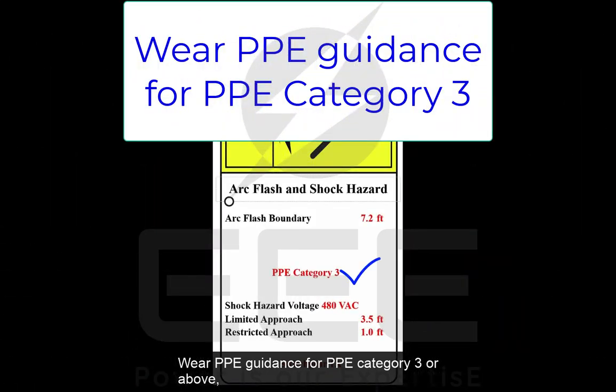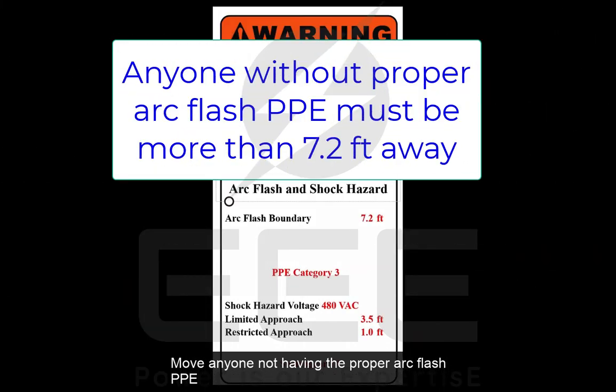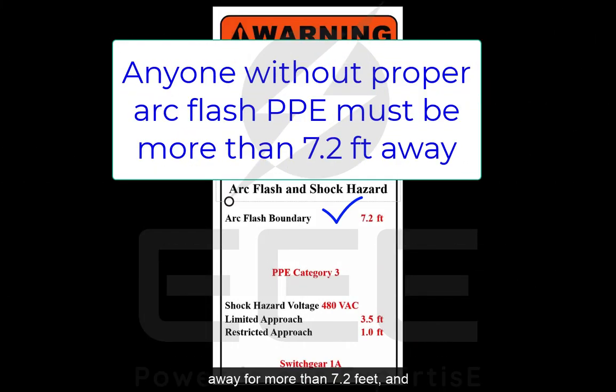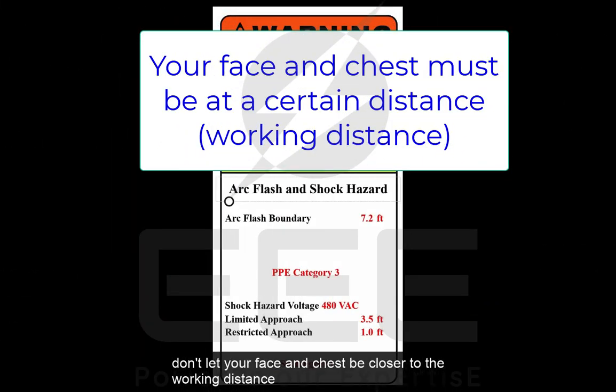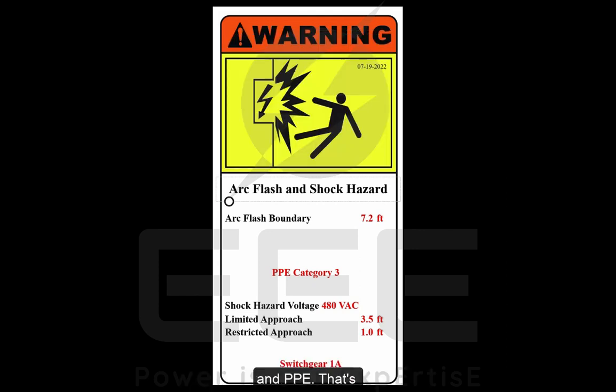Summary. Wear PPE guidance for PPE Category 3 or above. Move anyone not having the proper arc flash PPE away, more than 7.2 feet. And don't let your face and chest be closer than the working distance from the voltage source, and follow shock boundaries and PPE.